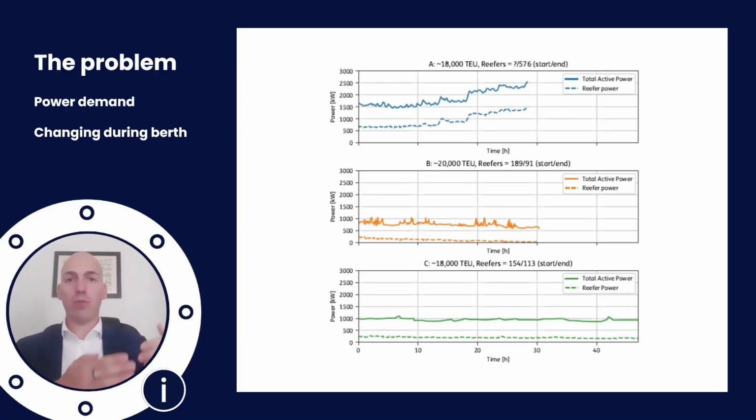And suppose you make calculations for a specific amount of reefers, refrigerated containers that go on board. I mean, that already changes. So if I have a ship that is capable of doing a lot of reefers but not using it, I get a totally different average power demand than a ship that has a lot of reefer capabilities and is typically using it a lot. Then I need to make a different business case looking at the investments needed from a shore strategy. So it's not just the table and how much it would be, but it's also how much do you actually use it in practice.